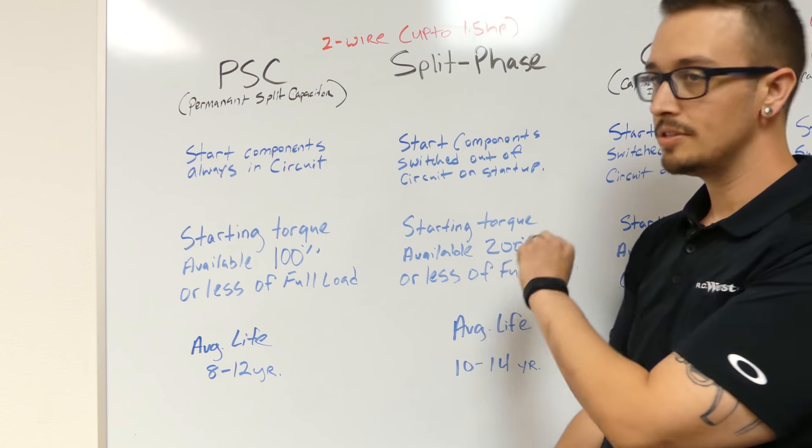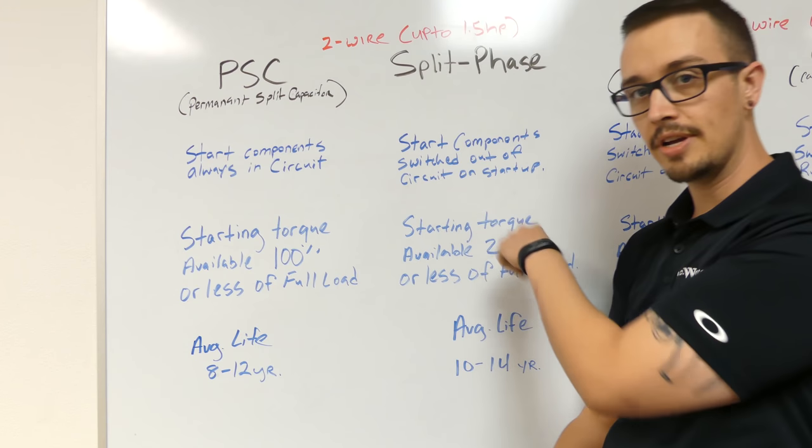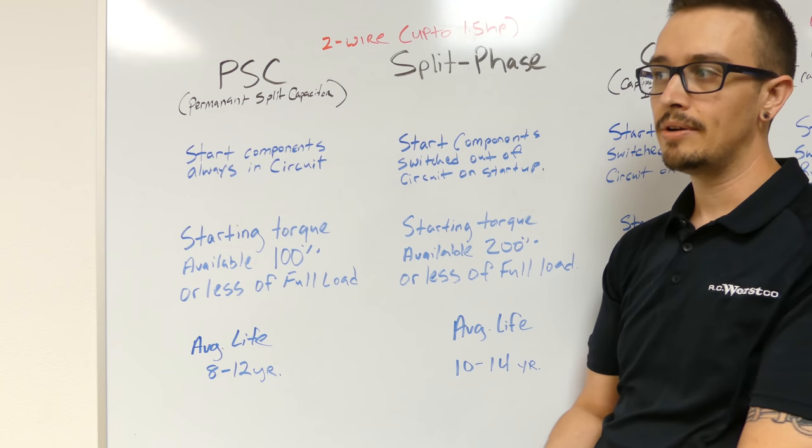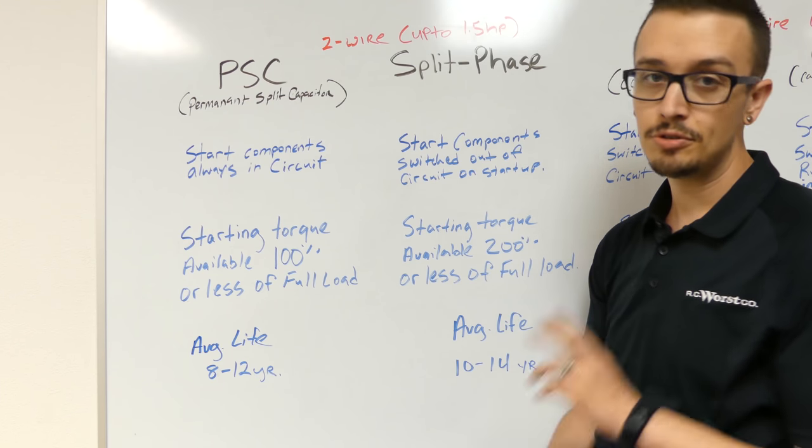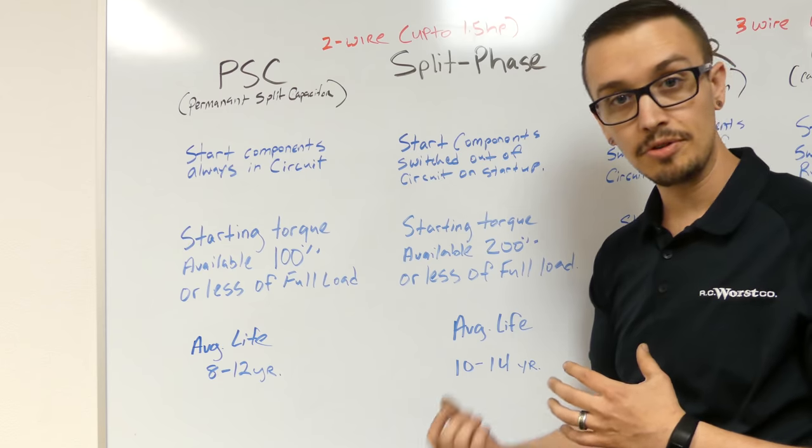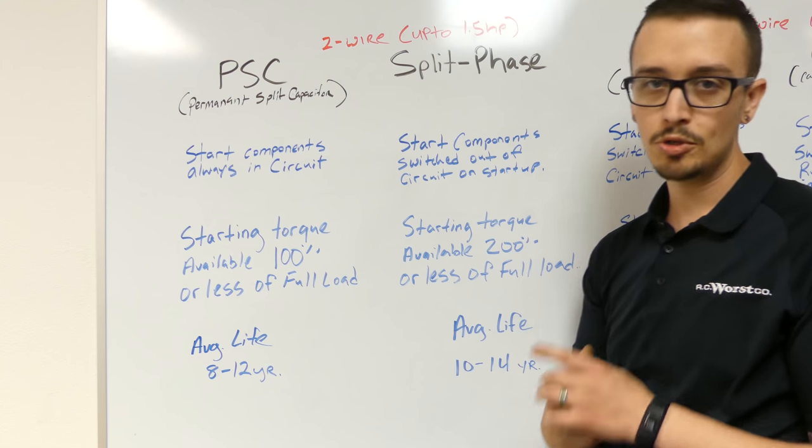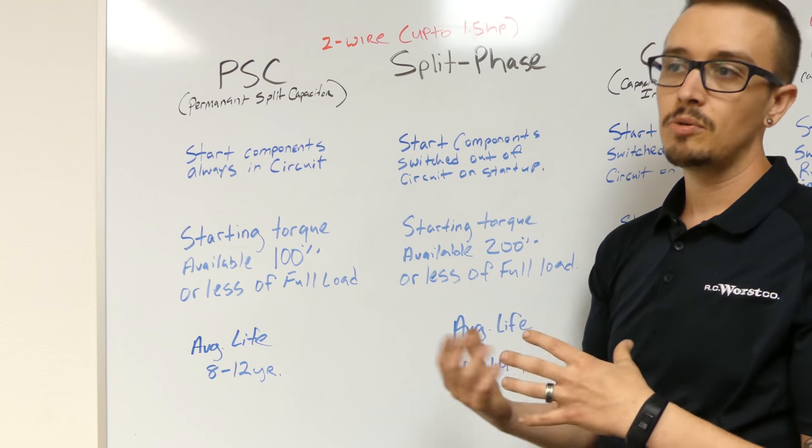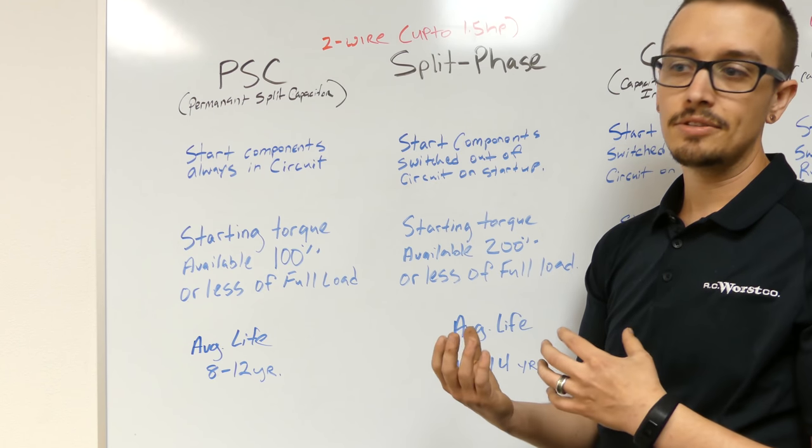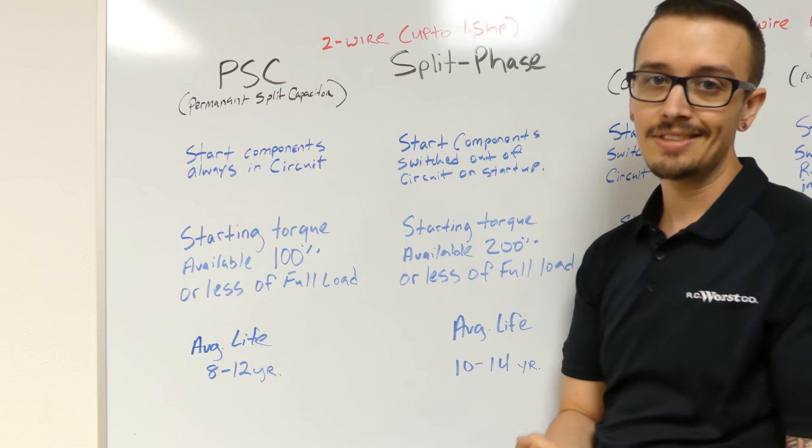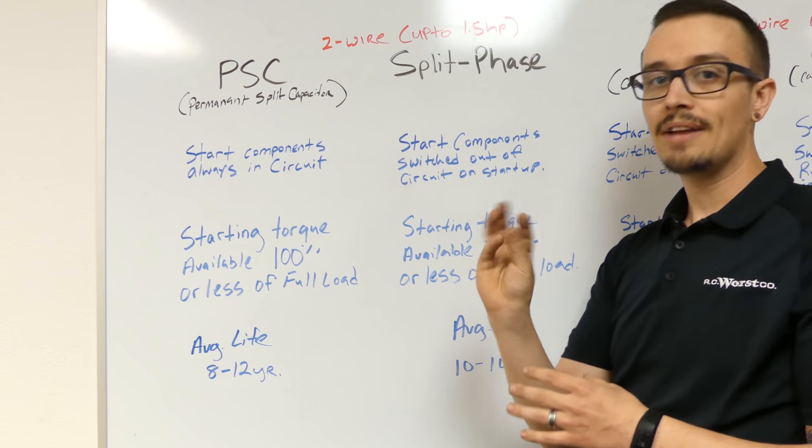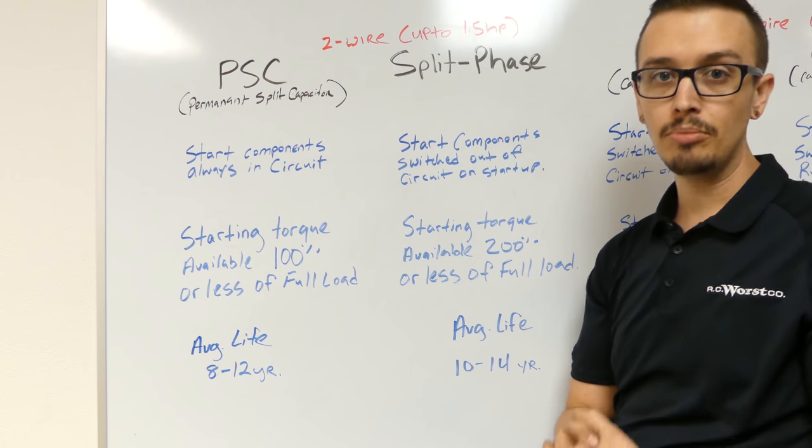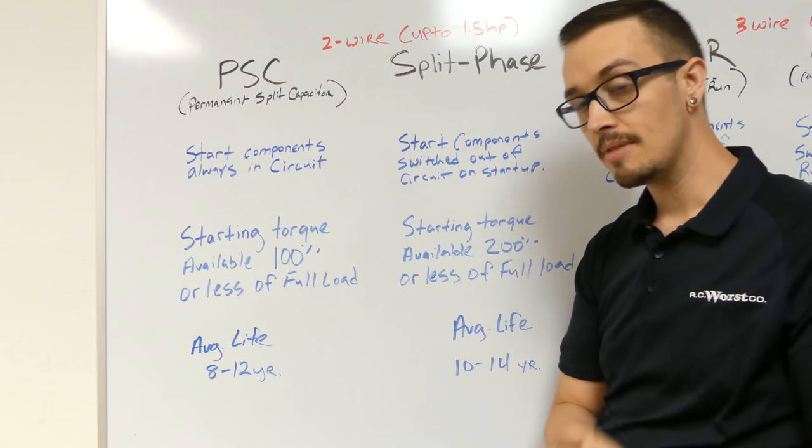The starting components on a split phase are actually switched out of the circuit on startup. I think the only people right now that are offering the split phase two wire motor design is Franklin Electric. And they use a very specialized switch when the starting components are switching out of circuit. And basically what that switch does is if the pump is bound up with sand or anything like that, it actually ratchets the shaft in an attempt to break loose anything that may be blocking the pump, which is a huge advantage over a PSC motor.